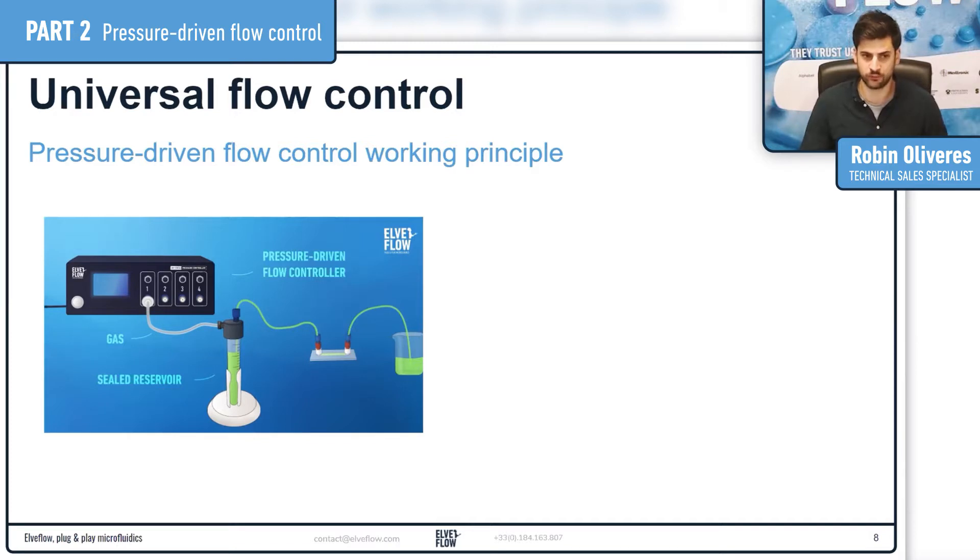You need to hook up your pressure controller to a high pressure supply - that can be any gas supply in a gas line in the lab or a compressor. Our pressure controller will then regulate this down to a very precise and stable output pressure that can be controlled.